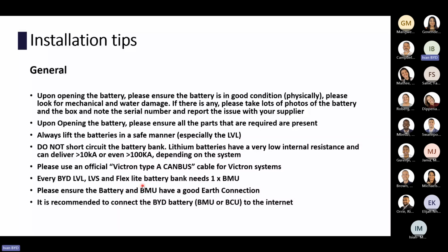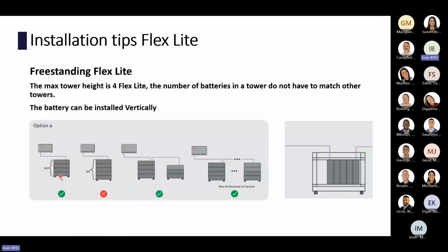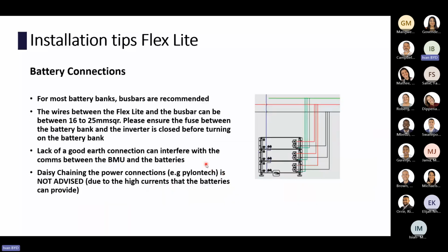In terms of how to install Flex Lite, you can have up to 4 in a tower, and then up to 64 in parallel. Here again, with the Flex Lite, it's not recommended to daisy chain the cables. I have seen it happen a few times. It's not recommended because of the amount of power these batteries can deliver. You can end up with a lot of current going through one connector. It's always recommended to go to a common point or a bus bar.